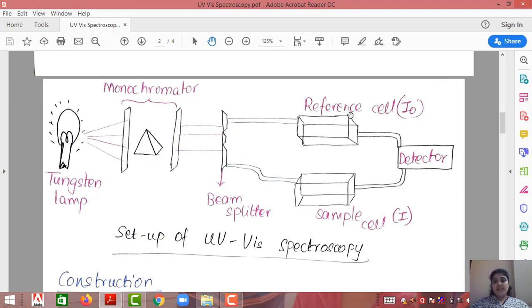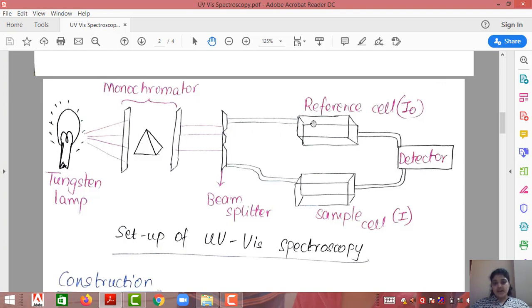We need to pass this parallel light through two different cells, so a beam splitter is placed in between. Whatever parallel light strikes the beam splitter is converted into two different light beams. One beam passes through the reference cell and the other passes through the sample cell. The output of the reference and the output of the sample are then given to the detector, where both intensities are compared.